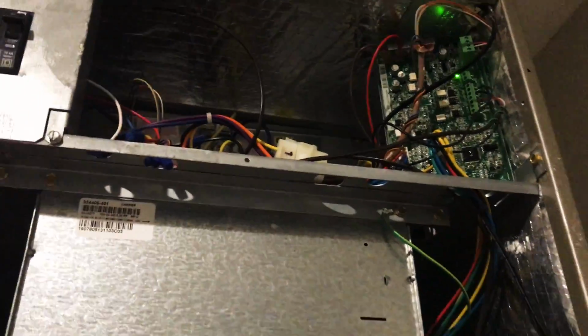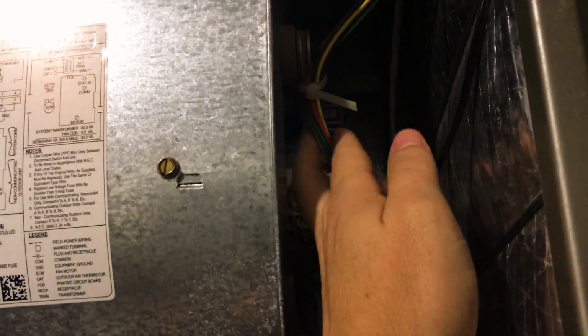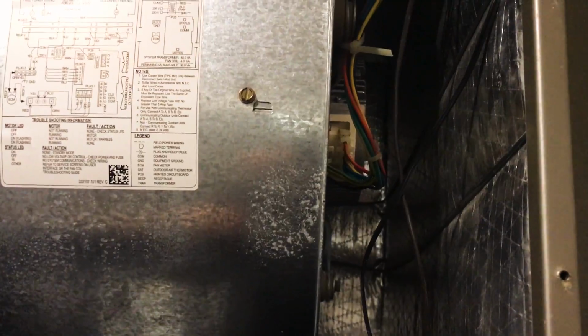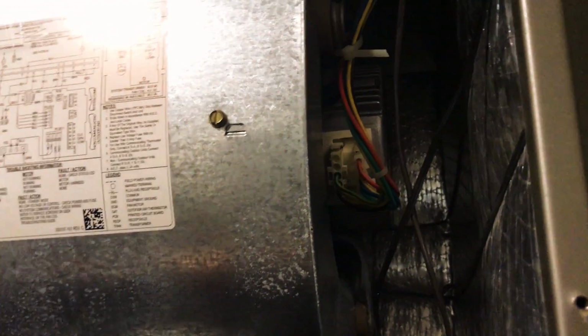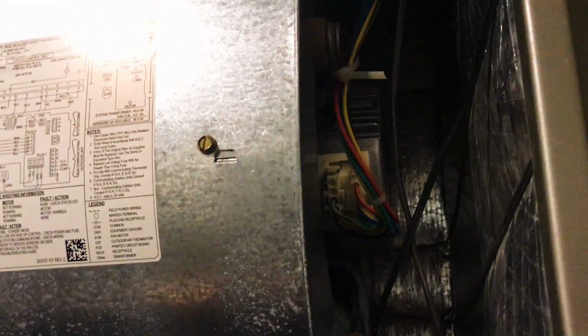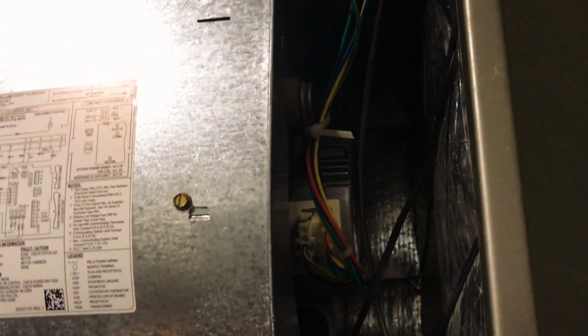I forced it into operation using the thermostat, and it's still not communicating. Now, one interesting thing is I didn't have a proper drip loop on it, as much as I preach about it. Another interesting thing is I did a video last night, and I was trying to show some maximum airflow, and so I had set the thing up for maximum airflow, and then I forgot to set it back. But I mean, it's still within the range of operation of this unit. It was running a little higher static pressure, I think 0.7, something like that. But then this morning I wake up and I have that communication fault.